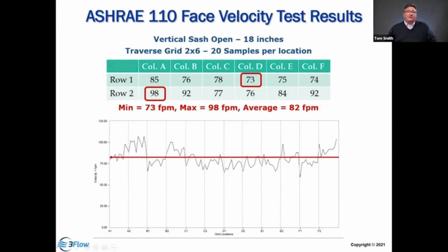So we look at this and we add up, divide by the number of measurements, and that gives us our overall average. So 82 feet per minute was our average, but our range was 73 to 98. Generally, we want velocities to be within plus or minus 20% of our average. Right? So in this case, with 80, we could go down 16 one way or the other. And that would give us a uniform distribution of velocity. Now, some hoods are designed for non-uniform distribution. We need to know that in advance.